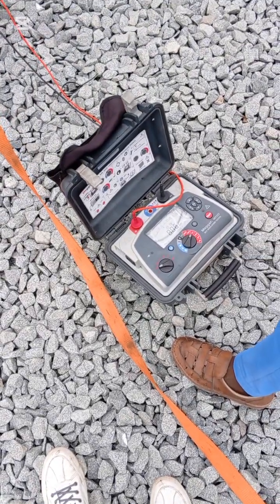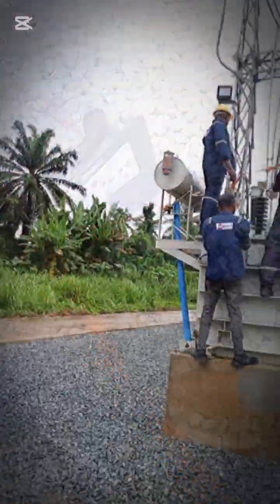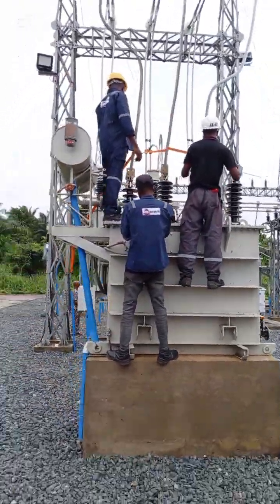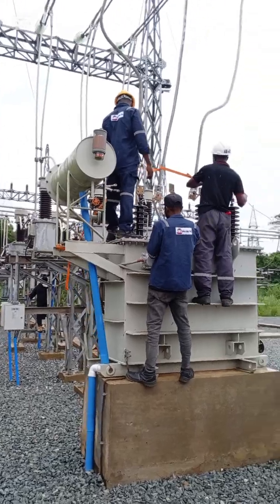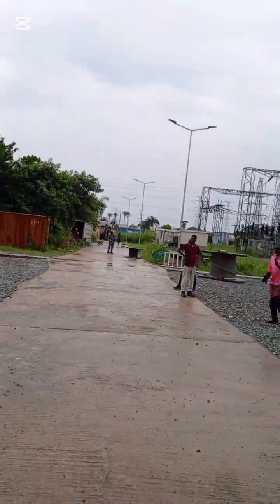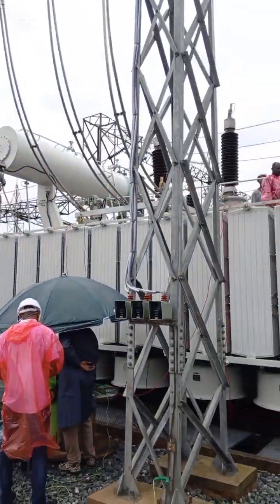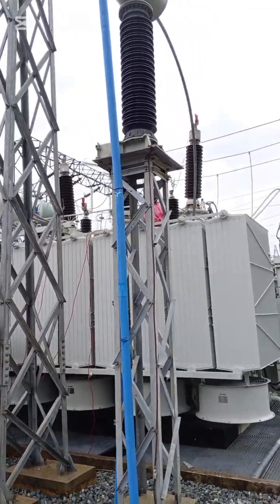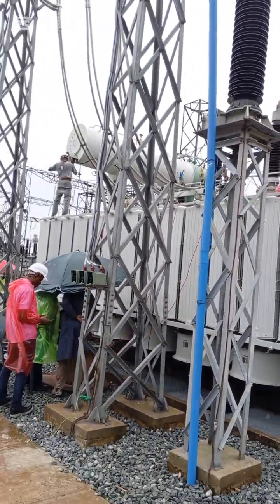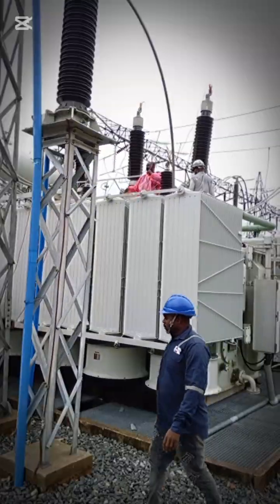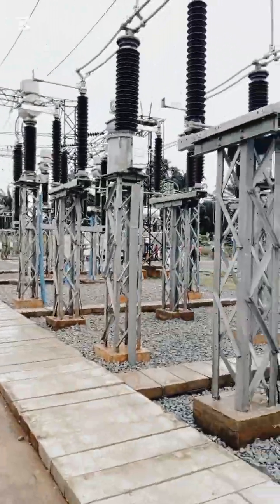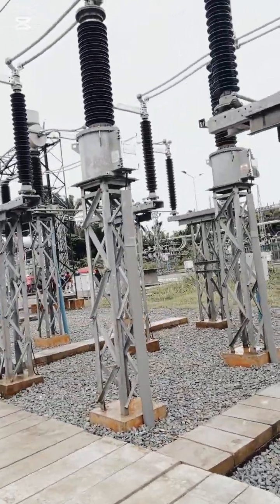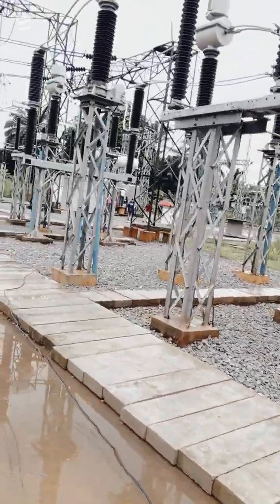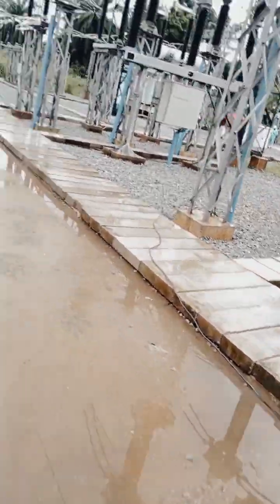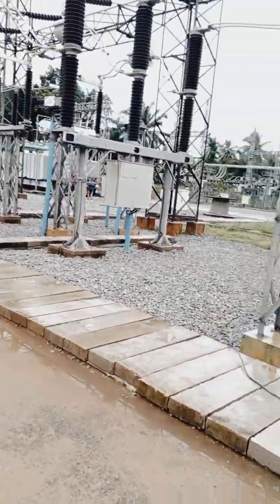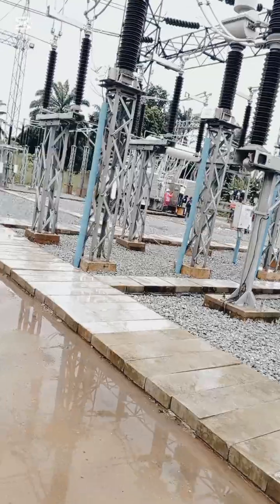Part 1: critical visual and mechanical inspections before oil filling and electrical tests. These might seem basic, but they are the first line of defense and can prevent major issues. 1. Thorough visual inspection. Check for any physical damage, dents, leaks, scratches from shipping or installation. Check for correct assembly of all components: bushings, radiators, fans, pumps, conservator, OLTC. Confirm all valves and oil and air release are in their correct positions.